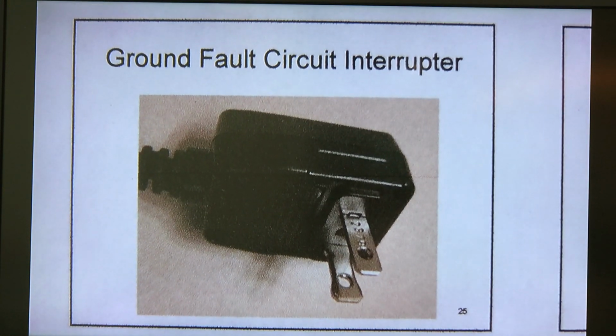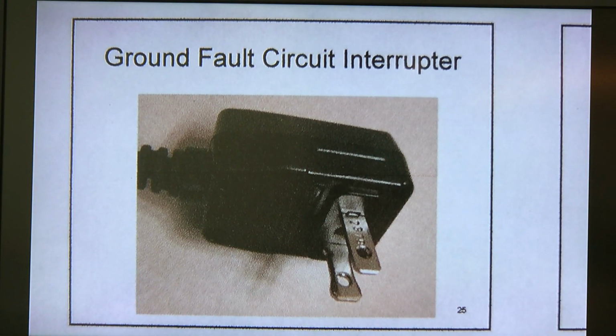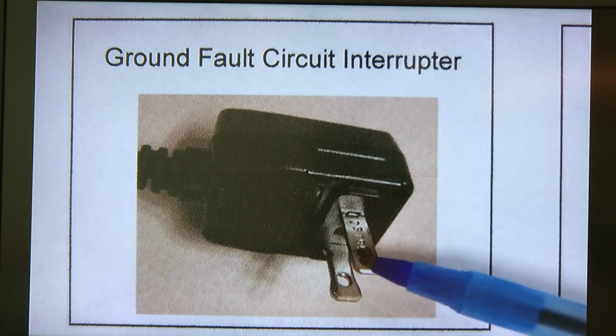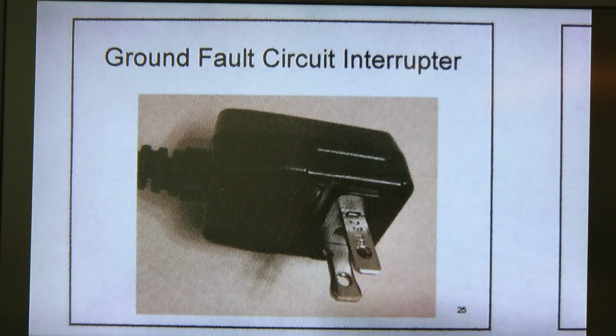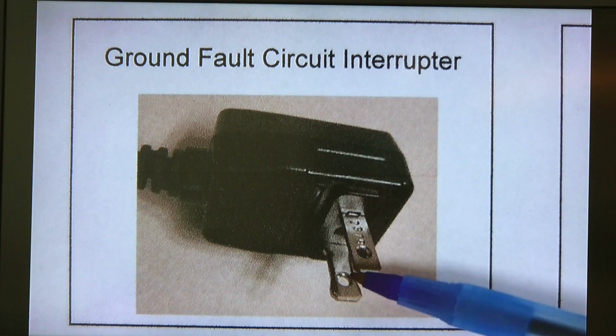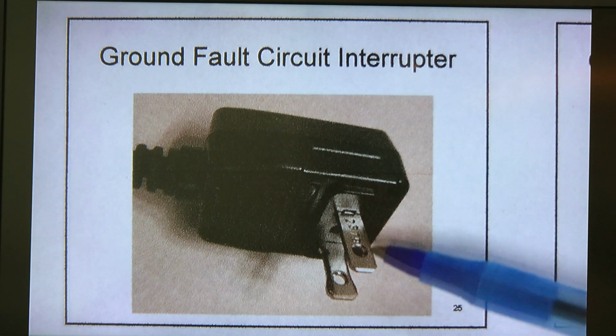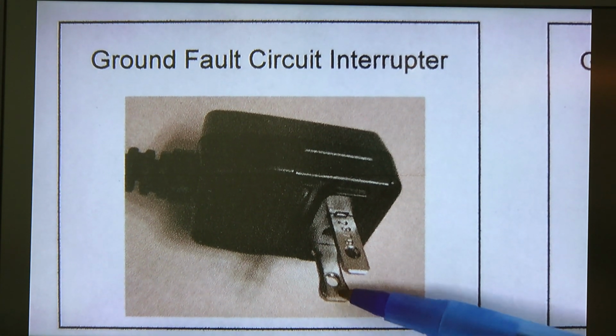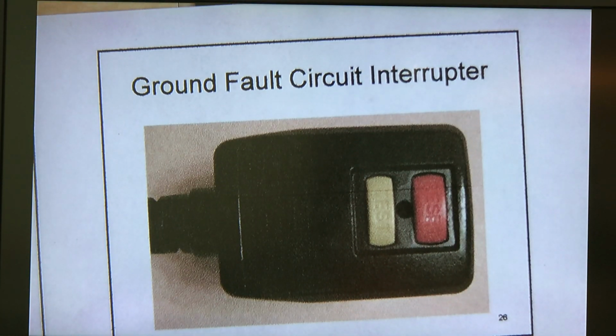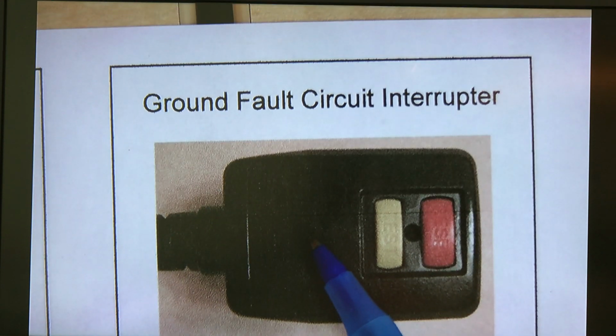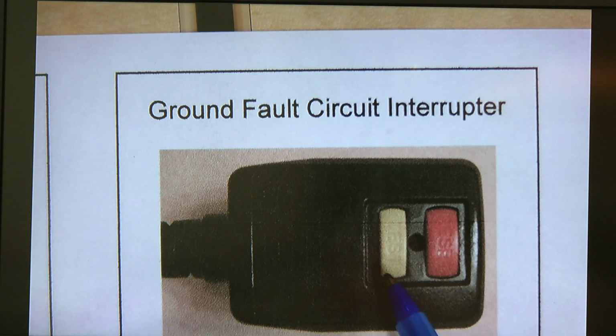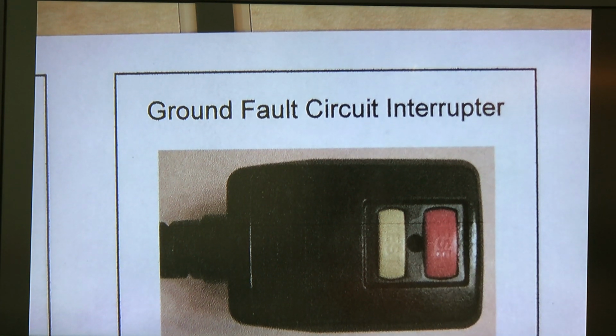Some things like hair dryers, for example, and this is one such plug, have a built-in GFCI connection. So what we're looking at here is a device that's meant to operate, and it's double insulated is one other requirement. Notice that we have this little thing down here that's wider than this one. This down in here is the neutral. This is the hot lead. And if you take a look at the other side of it, what you'll see is that you have a ground fault circuit interrupter built into the cable itself that also has a test button and a reset button. And it's not uncommon to have these things trip when you first plug them in. So probably a lot of you have had that experience.